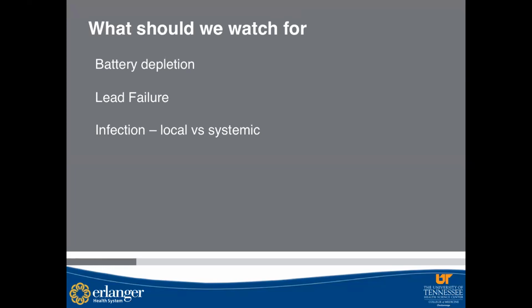We're making sure that the wires are actually working appropriately, because if the wires start breaking in some kind of way, either the outer coating goes bad or the inner wire that conducts the electrical sensation to the heart goes bad, then that lead would be in impending failure, and we would want to replace that with a new wire. That's part of our checking the device over time.